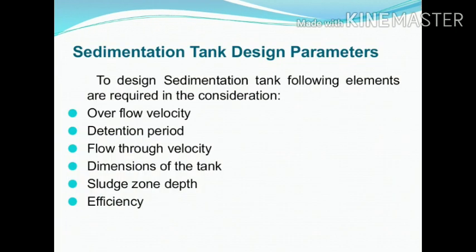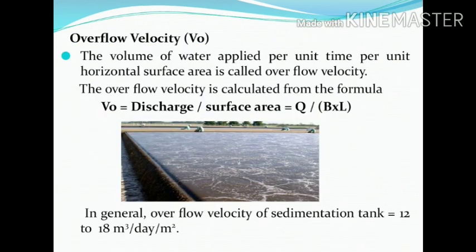Sedimentation tank design parameters. To design a sedimentation tank, the following elements are required: overflow velocity, detention period, flow-through velocity, dimensions of the tank, sludge zone depth, and efficiency. The first parameter is overflow velocity, denoted by V₀. The volume of water applied per unit time per unit horizontal surface area is called overflow velocity, also known as surface loading rate or surface overflow rate. The overflow rate must be less than the settling velocity of the particle; otherwise the particle will escape without settling.